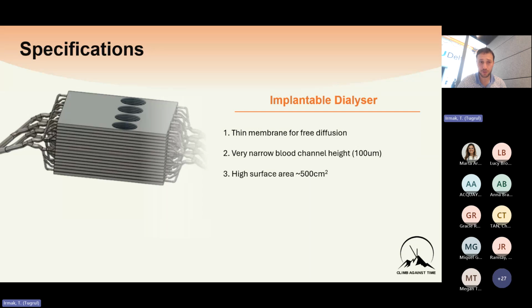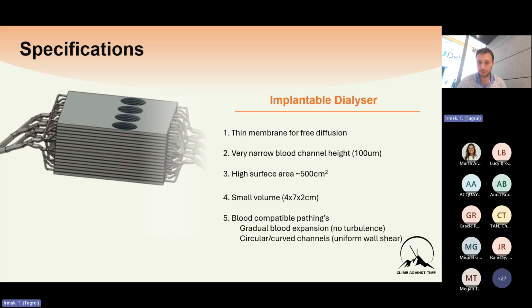But for an ultrafiltration device, which you also need an implantable dialyzer to be capable of, you need a high surface area. We need small volume, so as I said, 4 by 7 by 2, and blood-compatible pathways. So we can't have sudden expansions and contractions as in a current conventional dialyzer, where you have blood entry into a cap, and then expansion, and then contraction down into the bundle. So we need gradual blood expansion, and this can be done using a physiological branching law like Murray's law. We need circular/curved channels, so uniform wall shear, essentially. So this is on the device side, and also blood-compatible material, so no contact activation.